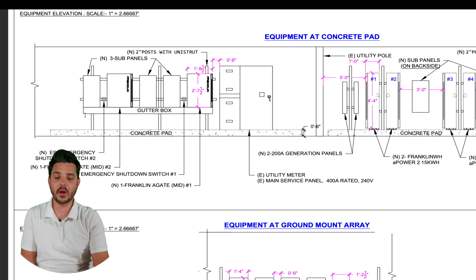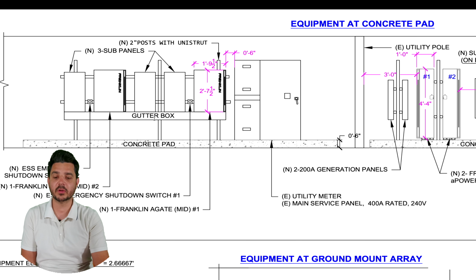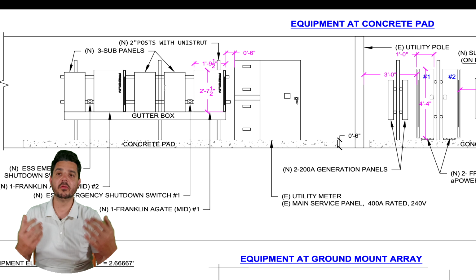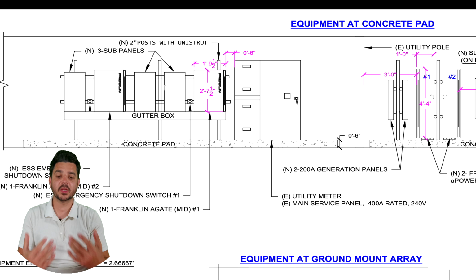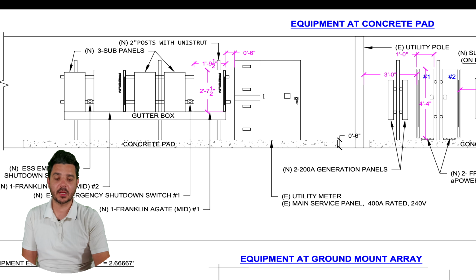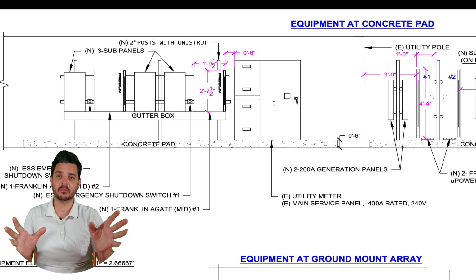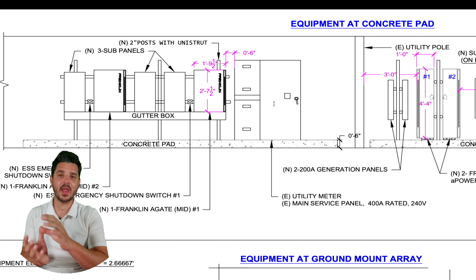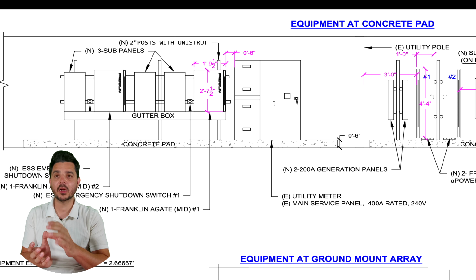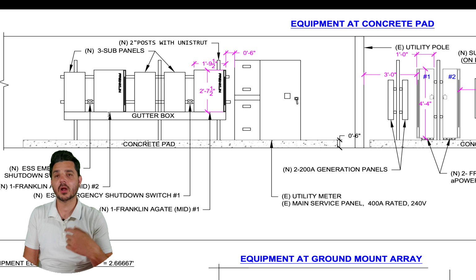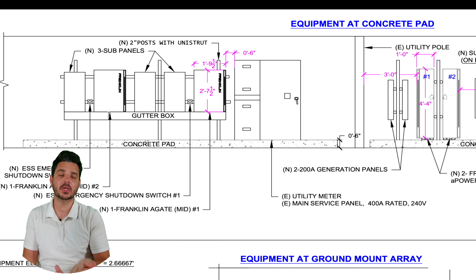Now some of this is already in place, so these unistrut 2-inch posts, those are already technically there, but we're going to be reconfiguring it, removing some of the existing equipment that's on site and replacing it with this new equipment. We got a massive gutter box, which we're going to need, and then we have the 2 sub panels, and this is the 400 amp service that's existing. This thing's crazy. It literally is 400 amps for a main gear, and it splits off into a couple sub panels down below that go throughout the property and the home, but there's two main 200 amp breakers that go into a 400 amp automatic transfer switch, because that's what's currently there for the generator.